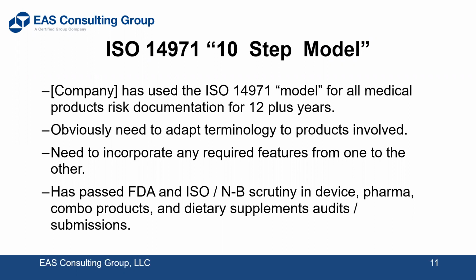Right now, your industry is doing quality manuals. Quality manuals are not mentioned in the GMPs. They're doing many other things. Risk management isn't specifically called out; having a risk management file isn't called out in design control, for example, 820.30, but it's expected. And even usability engineering is expected per the FDA and per the European Union, even though it's not specifically called out in 820.30 or in 13485 7.3, design and development planning, which is identical to the requirements of design control in 820.30.